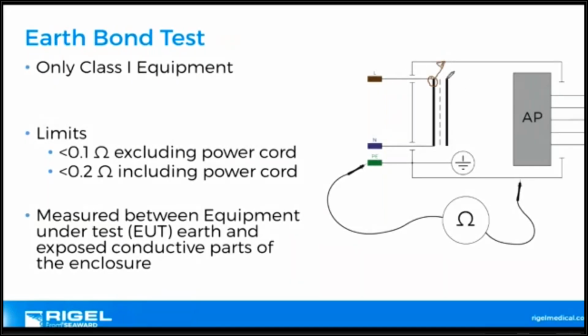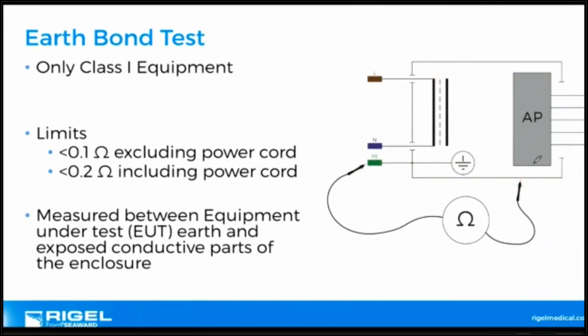Well, all of a sudden, you've got all of this current flowing around the device, hopefully going down to the protective earth, and this would take out the breaker. So your protective earth here is vital to be intact. If the protective earth was to go open circuit, we don't have an earth. Let's say it's not a short circuit, the only way current flows in this type of fault condition is via some of the stray capacitance that we talked about. If I'm touching this part of the chassis, or any part of the chassis that's conductive, I'm not going to be touching earth. So any fault current is going to flow through me. This is why we need to make sure that protective earth is intact and has a really low resistance.